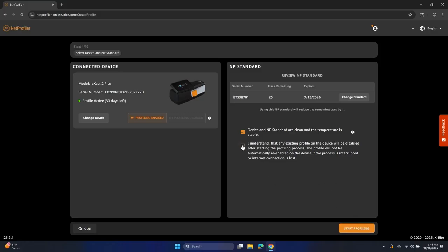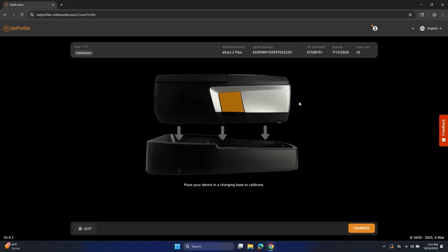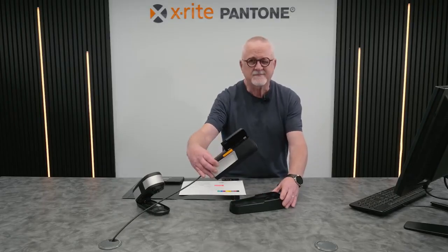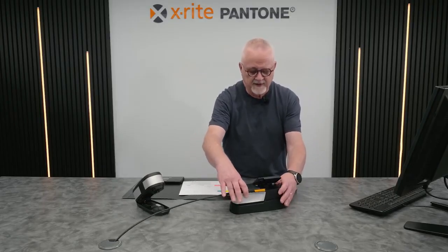We need you to be aware that that profile will be gone because we need to get rid of it so we can build a new one. Okay, so we're going to start profiling. And the first thing it's going to do is, it says, place your device in a charging base to calibrate. So that's this. That has the calibration standard in it. Okay, so I'm going to put it in place. I'm going to click on Calibrate.